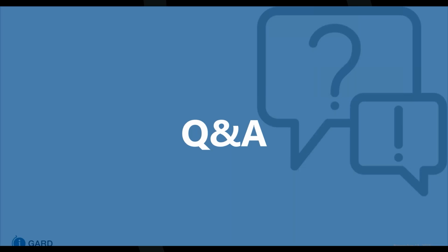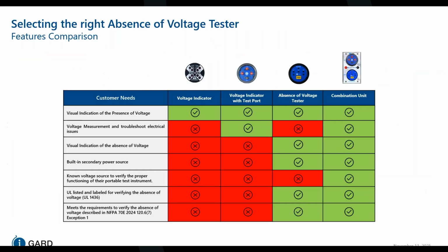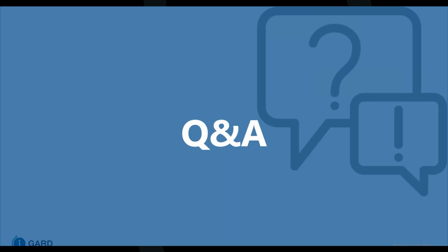Would this device be acceptable to use getting its voltage signal from PTs instead of direct from the bus? Unfortunately, we cannot use PTs in this arrangement because UL 1436 does not allow PTs to be utilized. So we have to actually connect directly to the point of work on the bus.